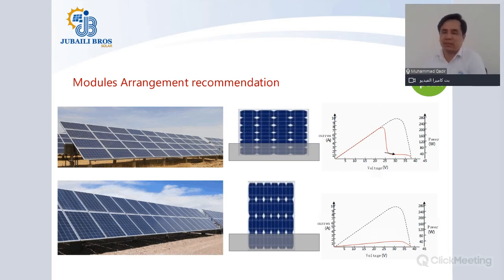Normally, shading in a ground mount is taken care of properly, but still, in the winter seasons, early in the morning or late in the afternoon, there is a slight possibility of shade from the front row to the back row. So in this scenario, you will get the benefit of higher production when you're installing your solar modules in the landscape method.